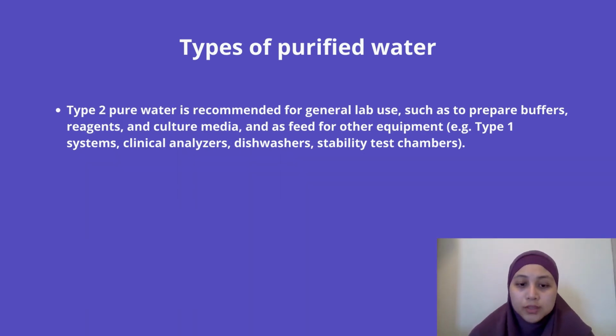Type 2 pure water is recommended for general lab use, such as to prepare buffers, reagents, culture media, and as feed for another equipment. Examples would be the type 1 system, the clinical analyzers, dishwashers, stability test chambers. So in this case, type 2 pure water can be used.